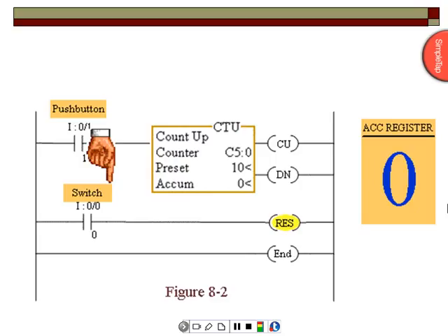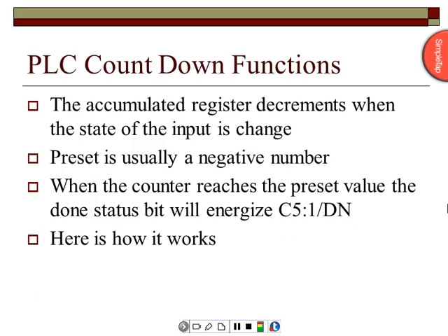So this is kind of like a retentive timer. You can't run it again until you reset it. Now what happens a lot of times is I get called back there. Y'all just tested it, made sure it works, but everything's on when I get back there because nobody reset it. And then you're throwing switches and trying to figure out why it's still on.